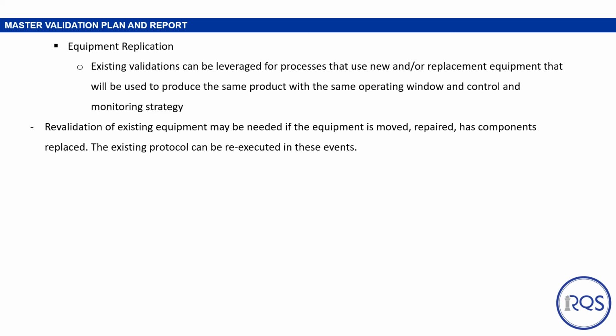Repeating full validation studies for the same processes offers no new knowledge or protection. Thus, existing validations can be leveraged for processes that use new and/or replacement equipment that will be used to produce the same product with the same operating window and control and monitoring strategy. So if you have equipment that is a replicate of existing equipment, you can use whatever validation plans and protocols have been established for that equipment instead of going through the whole process validation or process development phase all over again. Additionally, revalidation of existing equipment may be needed if equipment is moved, repaired, has components replaced, etc. The existing protocol can simply be re-executed in these events.